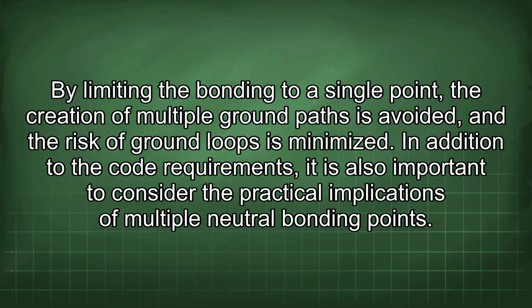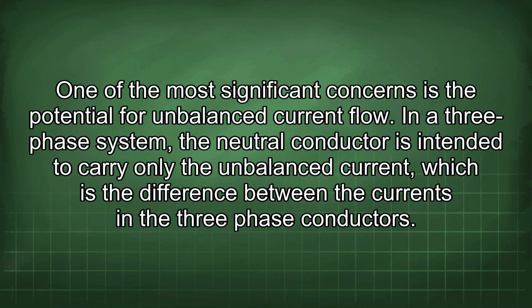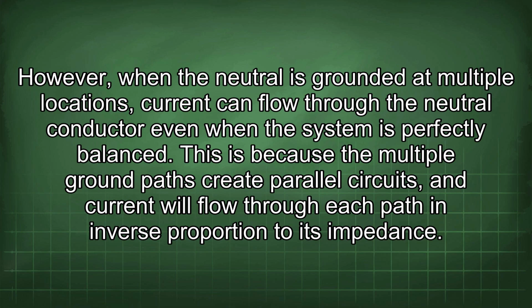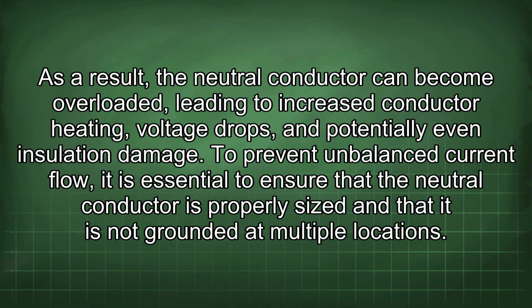In addition to the code requirements, it is also important to consider the practical implications of multiple neutral bonding points. One of the most significant concerns is the potential for unbalanced current flow. In a three-phase system, the neutral conductor is intended to carry only the imbalanced current, which is the difference between the currents in the three-phase conductors. However, when the neutral is grounded at multiple locations, current can flow through the neutral conductor even when the system is perfectly balanced. This is because the multiple ground paths create parallel circuits, and current will flow through each path in inverse proportion to its impedance. As a result, the neutral conductor can become overloaded, leading to increased conductor heating, voltage drops, and potentially even insulation damage. To prevent unbalanced current flow, it is essential to ensure that the neutral conductor is properly sized and that it is not grounded at multiple locations.